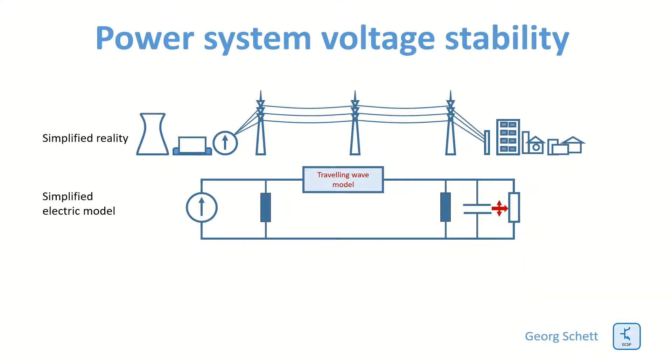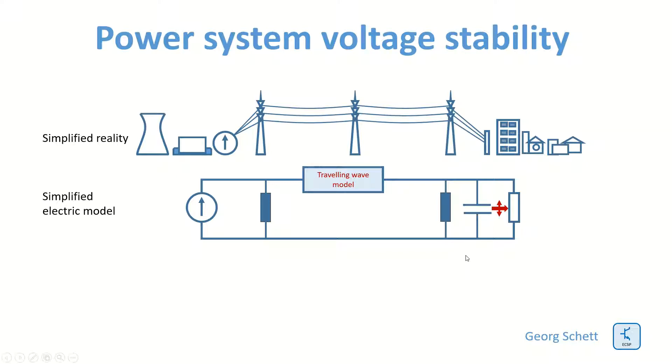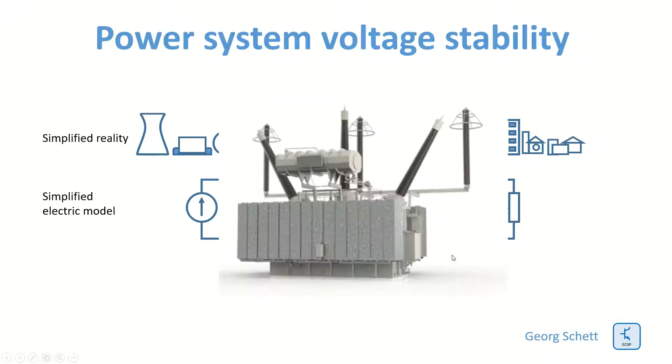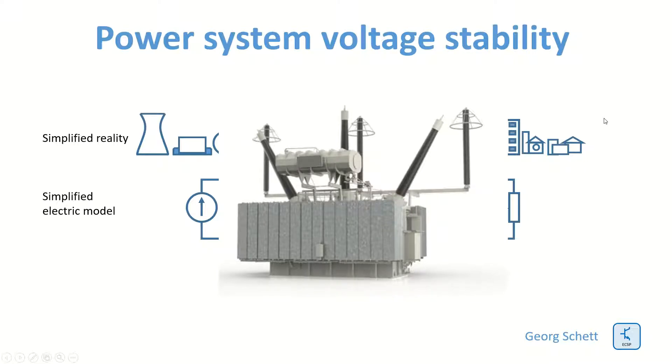So to compensate the reactive power in the system we need to have reactive power compensation. For over voltage we compensate by means of reactors. For under voltage we compensate by means of capacitors. These components can be placed normally at line ends within the frame of substations. They are quite big, these reactors for example here, and they are expensive but they are very important for the stability of the system.